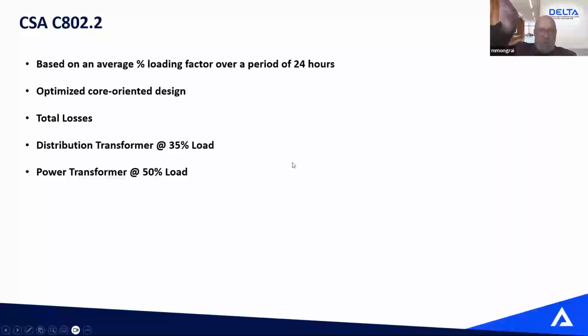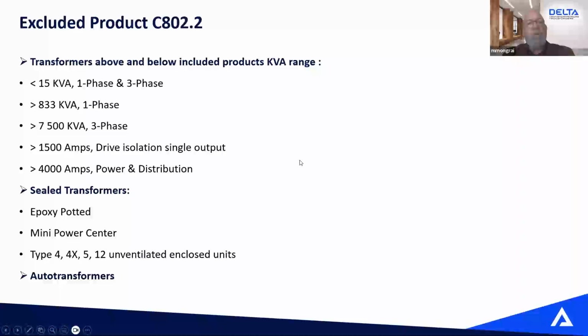So in that efficiency curve, sorry, the load curve, so from zero to full load, we need to meet that efficiency dictated by CSA at one point. So all the manufacturers will measure at one point, but we don't have the same curve. So it's important to understand how we calculate efficiency and what the losses of your transformer are when you want to compare apples to apples.